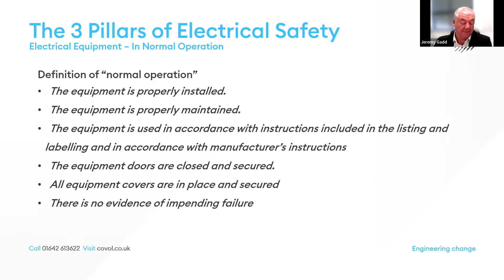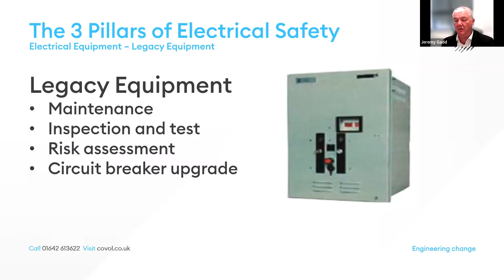Legacy equipment will need far more care, attention, and respect. This is due to its older age and potentially lower reliability. As with all equipment that is perhaps past its end of life, people do become complacent when addressing issues with it, because it's always been there and this is what we do and how we do it. This can also be a factor when dealing with legacy equipment.